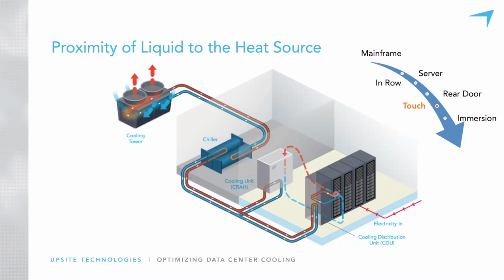There's still a fan running. Maybe it's only running at 20% of the speed that it would have run if it were purely air cooled, but there still might be a fan with some flow of air required to keep some of the components cool that liquid cannot pick up the heat from. So we have a true hybrid situation here where we have the two loops, one air and one liquid, picking up the heat from the source.